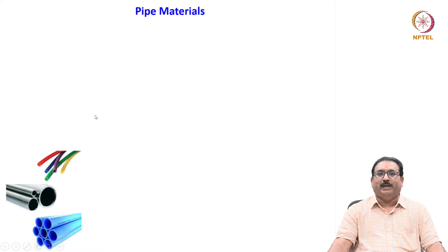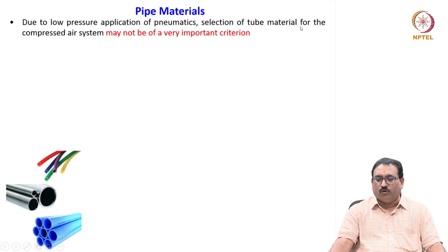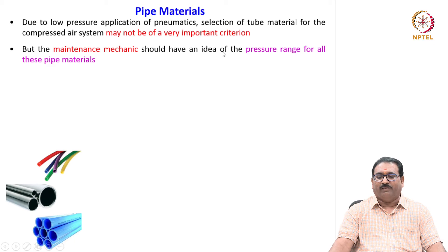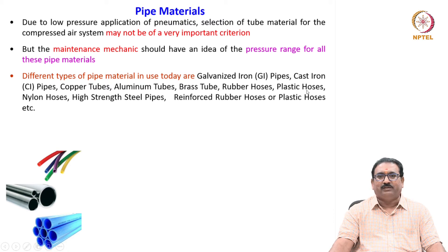Regarding materials for pipes and tubes: due to the low-pressure application of pneumatics — normal operating range is 6 to 10 bar, with people rarely exceeding 20 bar — the selection of tube material may not be a critical criterion. However, maintenance mechanics should know the pressure range for all pipe and tube materials. Different types in use today include galvanized iron (GI) pipes, cast iron (CI) pipes, copper tubes, aluminum tubes, brass tubes, rubber hoses, plastic hoses, nylon hoses, high-strength steel pipes, reinforced rubber hoses or plastic hoses, and many more.